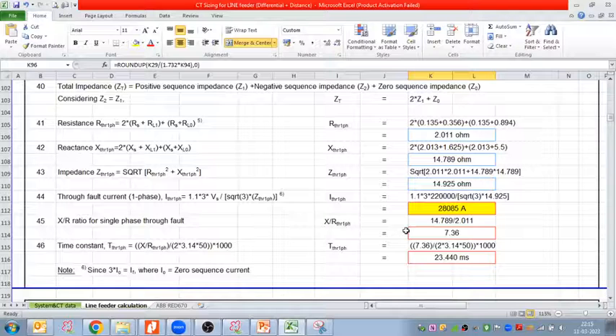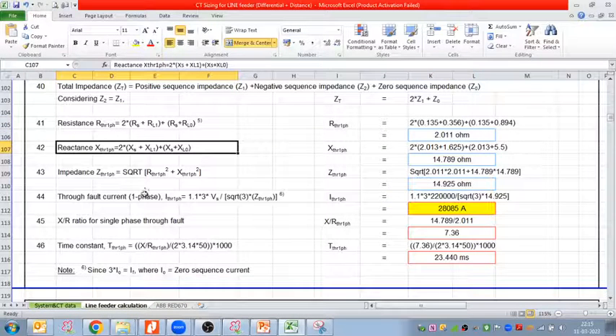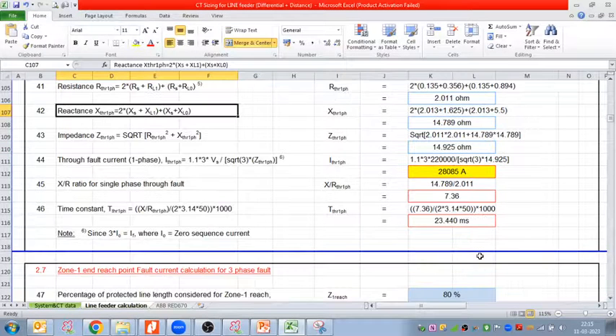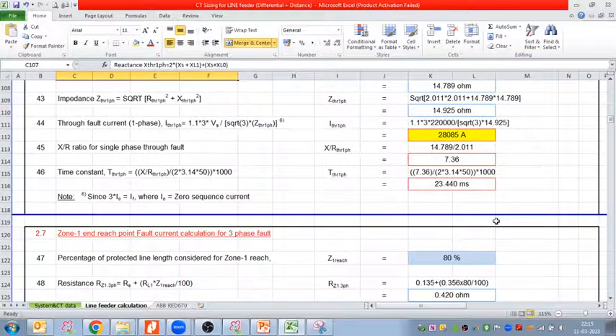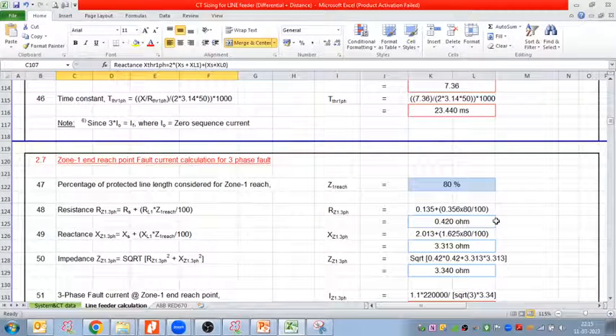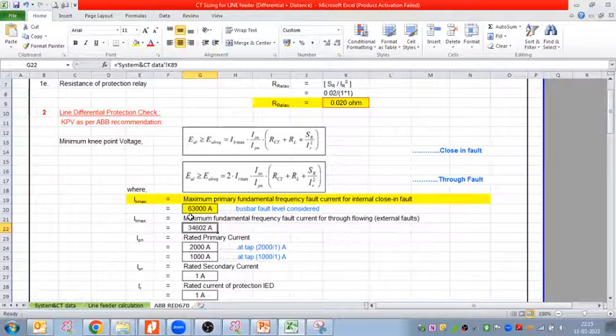But if you want to calculate, yes, here we have the formula. Source resistance plus resistance and reactance we can calculate, then impedance we can calculate, and then fault current we can calculate. But it is better to go with the three phase fault current. So once my three phase fault current is calculated, let's go to the calculations.